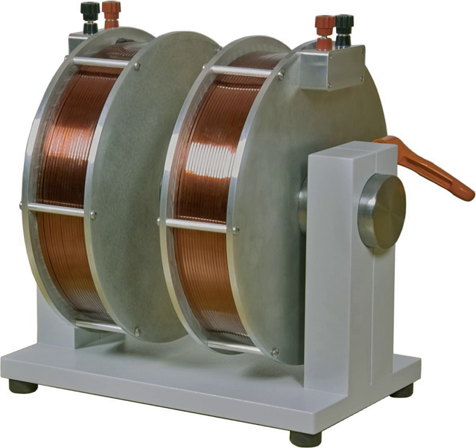With small electromagnets, a capacitor is sometimes used across the contacts, which reduces arcing by temporarily storing the current. More often a diode is used to prevent voltage spikes by providing a path for the current to recirculate through the winding until the energy is dissipated as heat. The diode is connected across the winding, oriented so it is reverse biased during steady-state operation and doesn't conduct. When the supply voltage is removed, the voltage spike forward biases the diode and the reactive current continues to flow through the winding, through the diode and back into the winding. A diode used in this way is called a freewheeling diode or flyback diode.